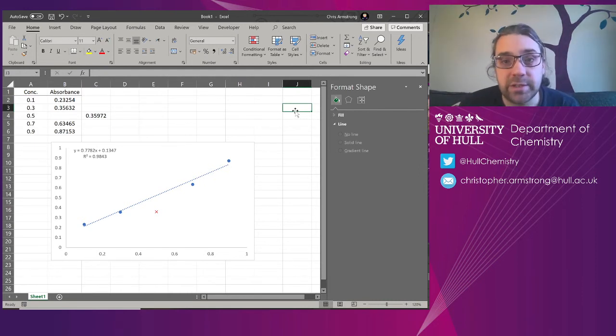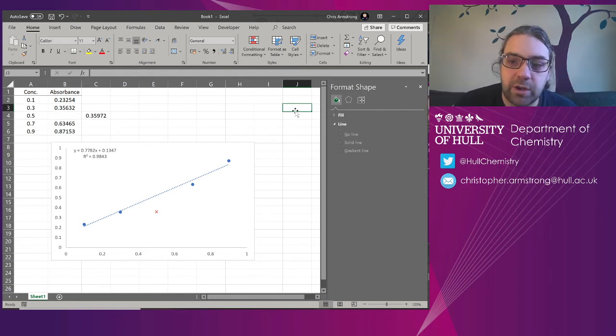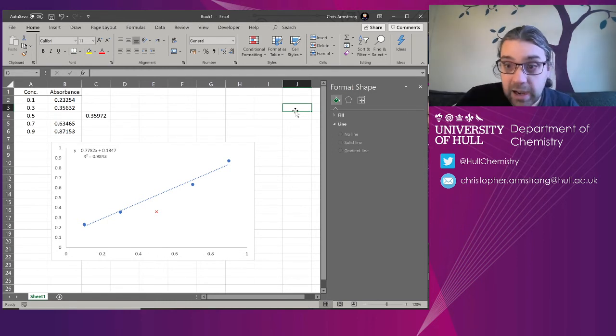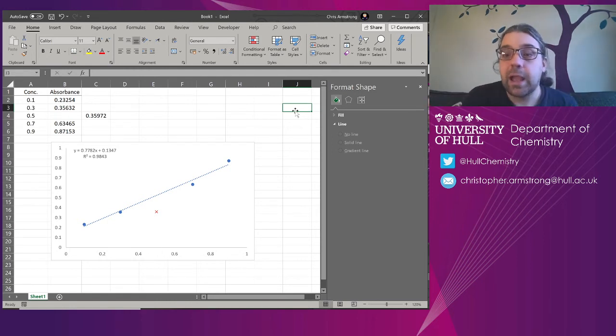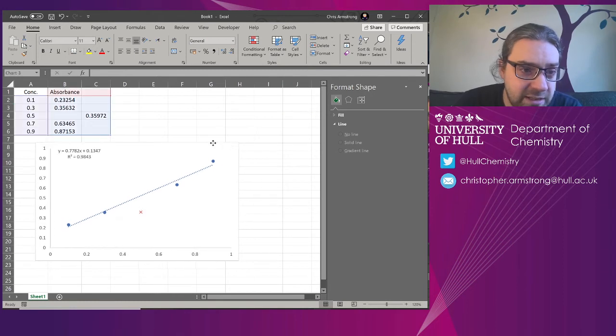I'll copy and paste it into a report. And underneath it will be figure 3 calibration graph. The red x means I've excluded the data point. And that would be how I would then go ahead and recommend that you present that. Works really nicely.